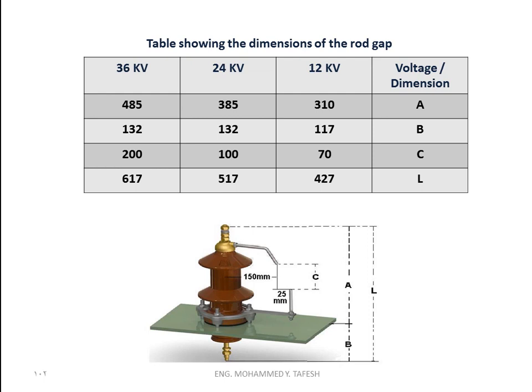This table shows us the dimensions and distances of the rod gap at this insulator. When our system is working on 24 kilovolts, you will find the dimension C is 100 millimeters. The dimension L — the full distance between the two terminals — is 517 millimeters. And the distance B between the surface of the transformer and the deep terminal in the oil in the transformer is 132 millimeters.